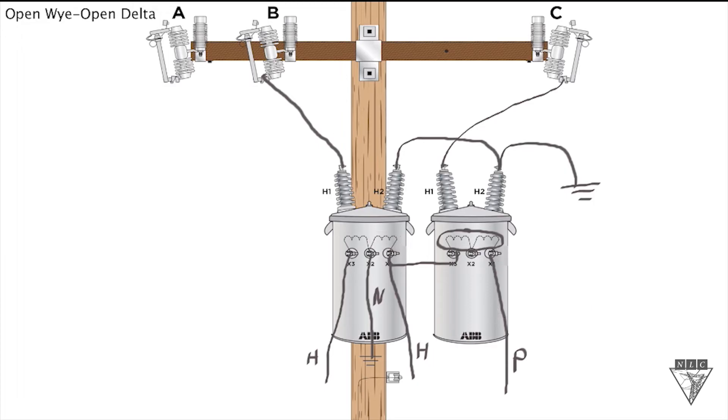The reason why that's important is predominantly an open bank is used where you have a single phase load that's the primary load, but then you also need some three phase power. That single phase load, which usually is like a home, you want to make sure and use the two hot legs and the neutral for that home.